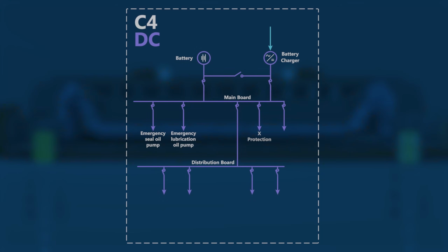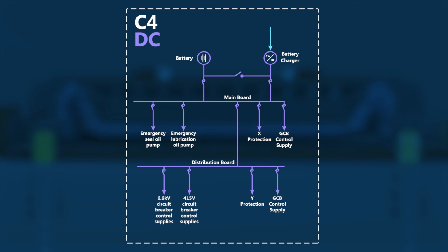Meanwhile, the DC system runs a range of control and monitoring systems critical for the safe operation of Unit C4. In simple terms, it powers the brain and life support system of the unit. The DC system runs the unit protection, which monitors the turbine generator for issues and takes appropriate action in response. The DC system also provides power to emergency backup systems. For example, it supplies emergency lubrication oil and seal oil pumps in the event of a loss of AC.